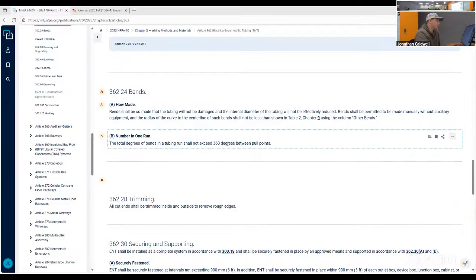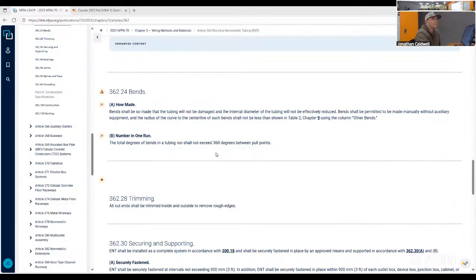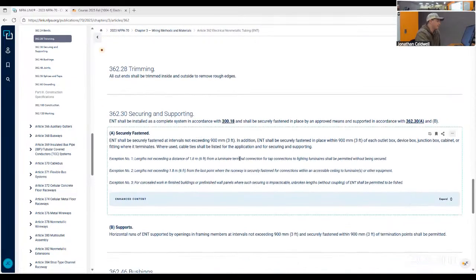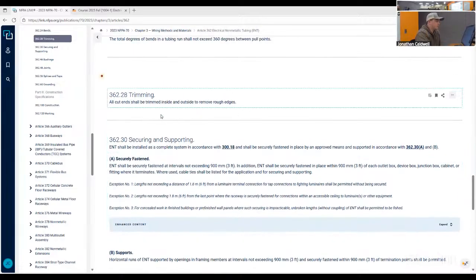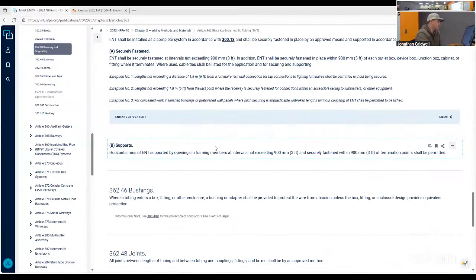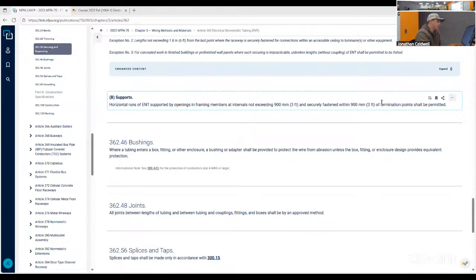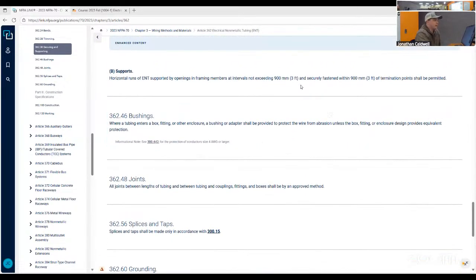Just the biggest thing with ENT, because you can go more than 6 feet, make sure your bends don't exceed 360 degrees. That's extremely important. And then just like PVC conduit, remove the rough edges and flex and all that. It has to be supported every 3 feet and 3 feet within the termination point. If you want a nice, clean, straight run, you have to do more. Because if anyone's ever dealt with ENT before, most of the time it comes in a coil, and if it doesn't come in a coil, it comes on a spool. And trying to bend that stuff straight does not work. The best I've seen is people take a PVC heater to it or heat it up in some form. It does real good, but it just does not play nice.